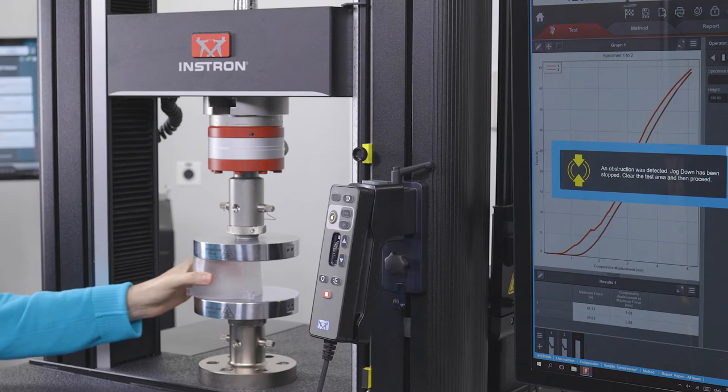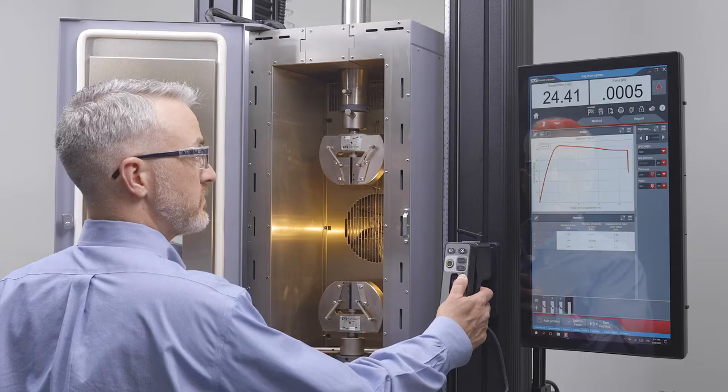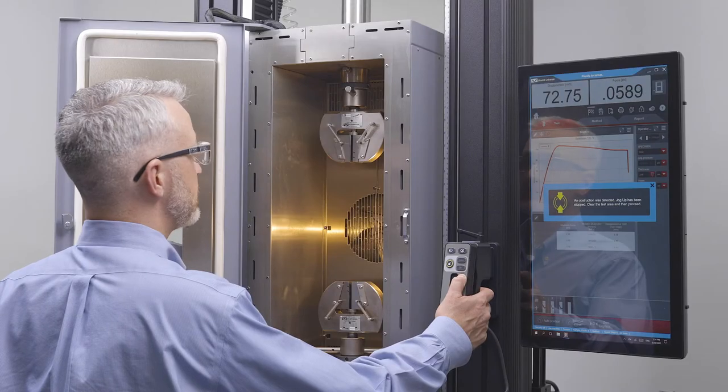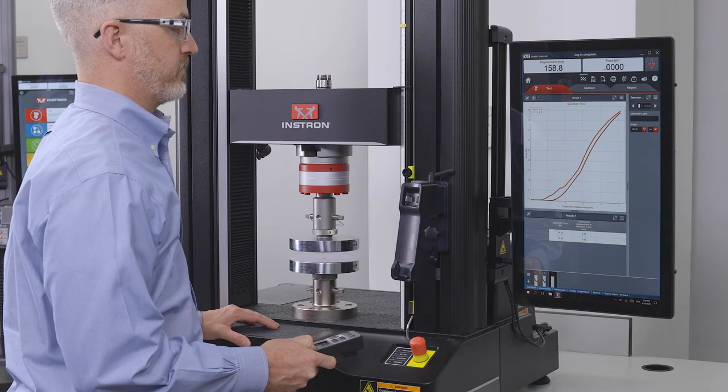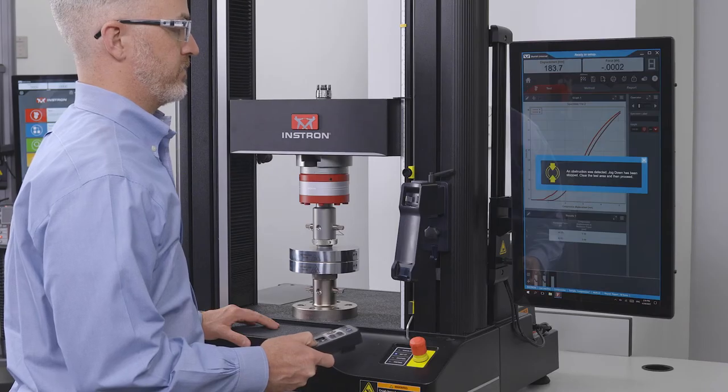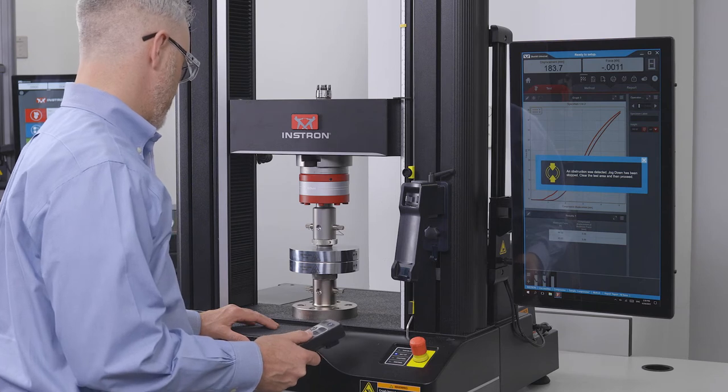Collision Mitigation works in both tension and compression. Its ability to protect the load cell and fixtures is highly dependent on the test setup. It has been rigorously tested and confirmed to protect load cells matching the capacity of the test frame for crosshead speeds up to 600 millimeters per minute.